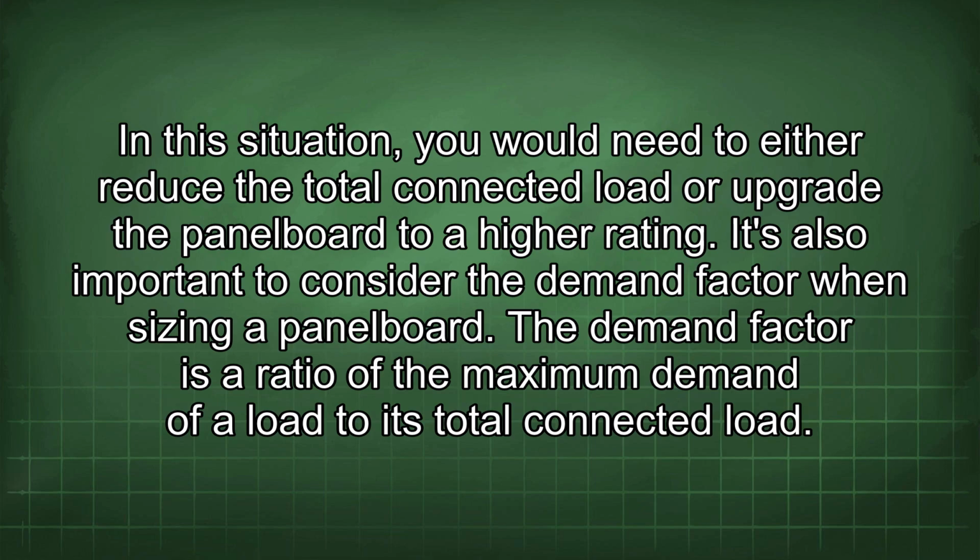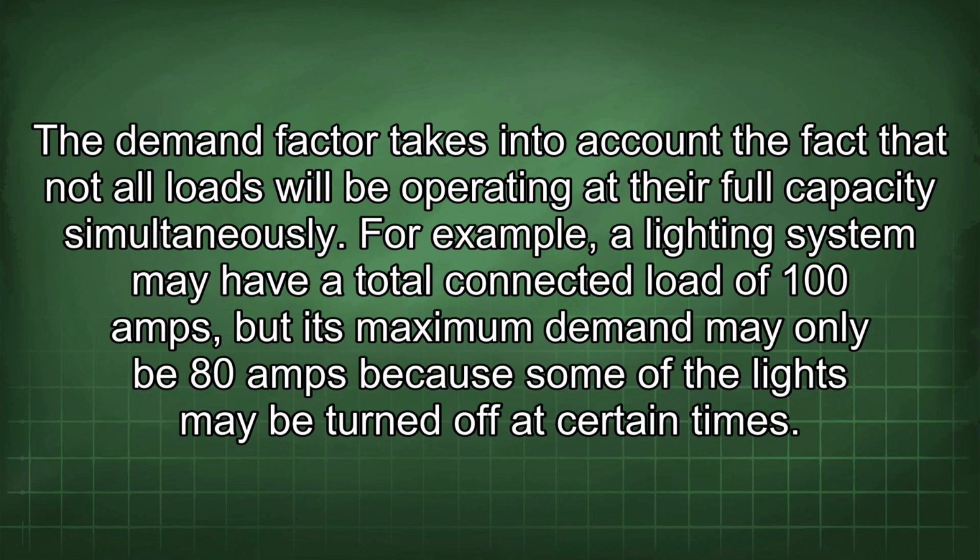It's also important to consider the demand factor when sizing a panel board. The demand factor is a ratio of the maximum demand of a load to its total connected load. The demand factor takes into account the fact that not all loads will be operating at their full capacity simultaneously. For example, a lighting system may have a total connected load of 100 amps, but its maximum demand may only be 80 amps because some of the lights may be turned off at certain times.